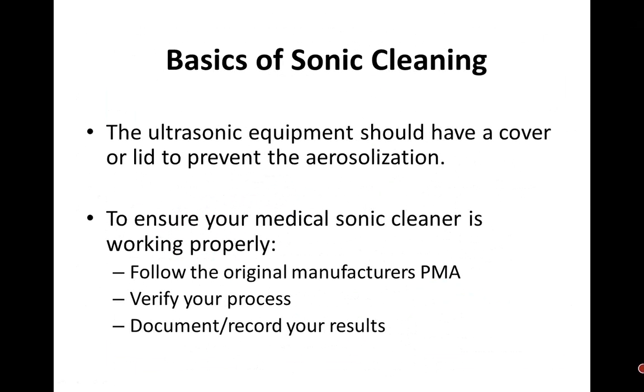The ultrasonic equipment should always have a cover or lid to prevent aerosolization, whether it's a tabletop or a big unit. You put that back on there to prevent the aerosolization. To ensure the medical sonic cleaner is working properly, what do I say? Follow the original manufacturer's IFU, but also follow the PMA. And I have found, and it is a shame, that sonic cleaners seem to be like the stepchild in sterile processing. We don't tend to follow the preventive maintenance, and in the pictures I see, the neglect is clear. It's done on an as-needed basis, when it breaks down. Many people think as long as it's humming and working, it's working, and I'm going to show you different.